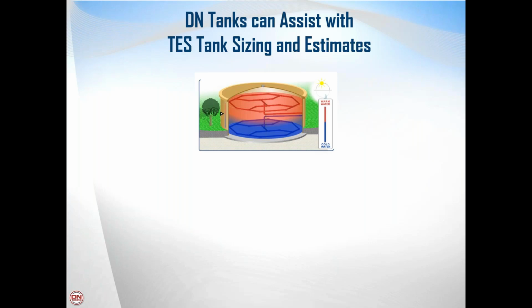And then one other advantage for ice that the owner might want to consider is you can provide colder water to the system. Instead of utilizing 40 to 45 degree supply water for cooling, you could actually have colder water, which would include this brine type solution with the ice system, and you could cool at lower temperatures, which could help on the dehumidification side. So space is the number one reason. If it's a very small system, like a small building, ice is another good example of where it comes into play, or a very low temperature dehumidification type application. But if you have to use the propylene glycol, you're going to lose 10% on your power, right? Correct. You're going to pay an energy penalty with ice, no matter what you do.